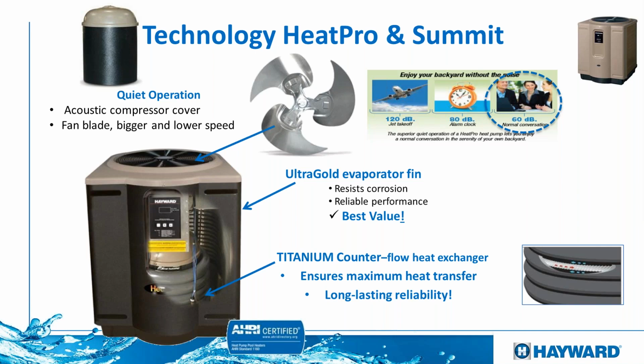Another big benefit that we have is the ultra gold evaporator fin. That ultra gold, what it does, it is very corrosion resistant. So when you are installing our heat pump close to the sea, close to the beach, or you are installing it in an area with very high humidity, that ultra gold evaporator is going to have a better performance, and it is not going to corrode as quickly as you will normally see with the competitor products.